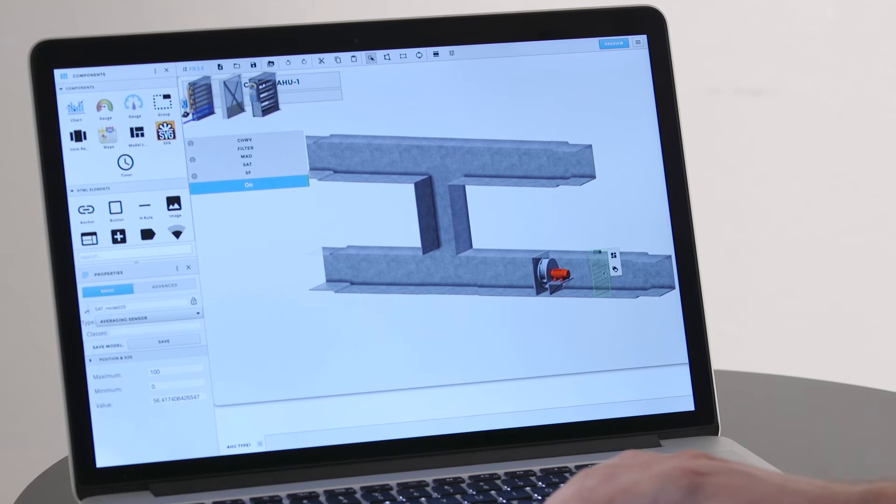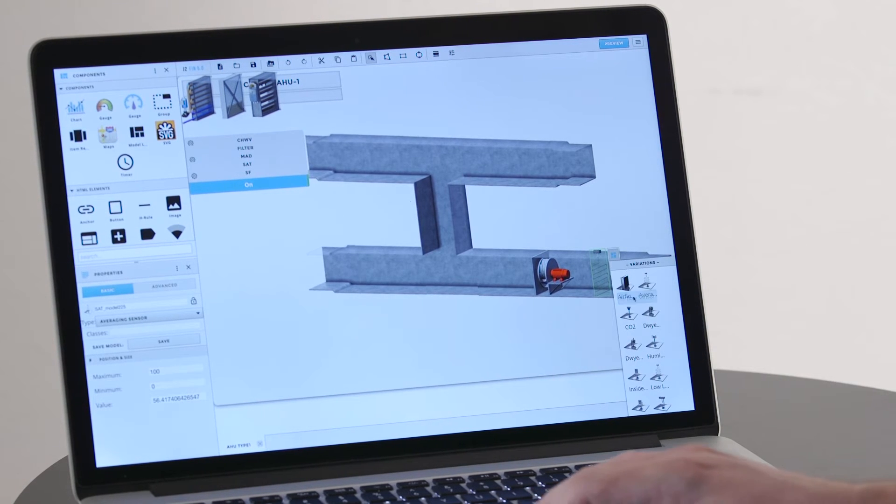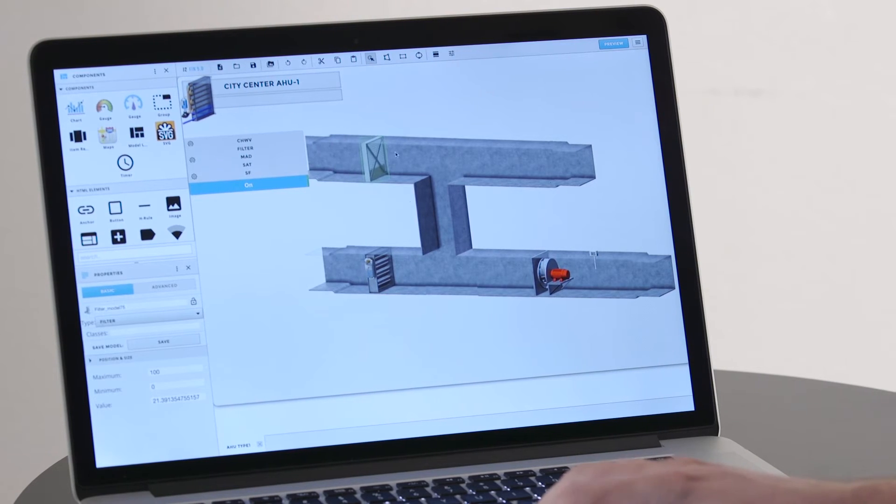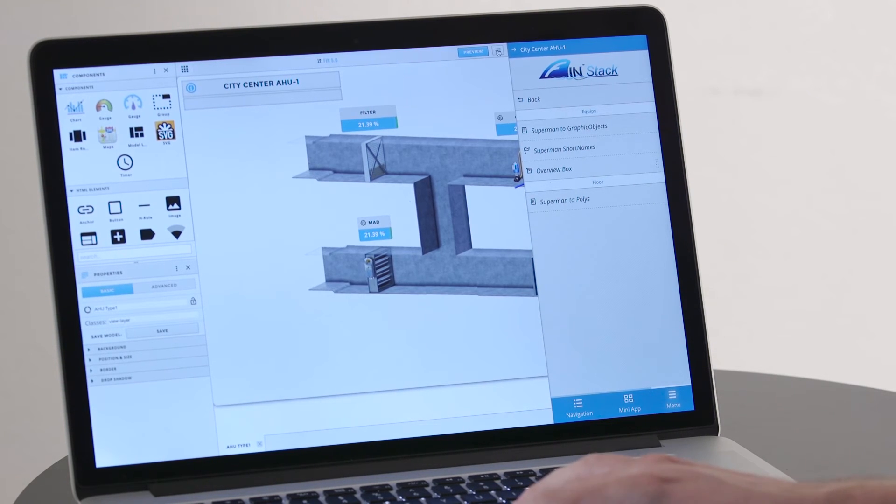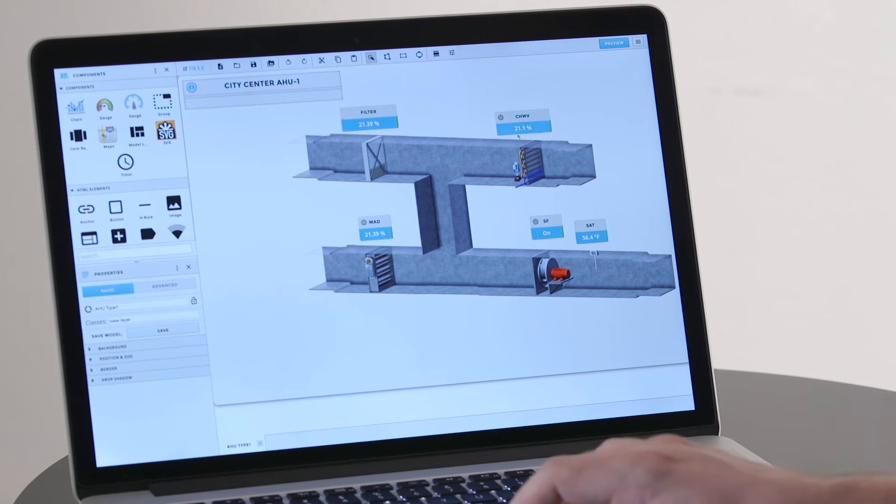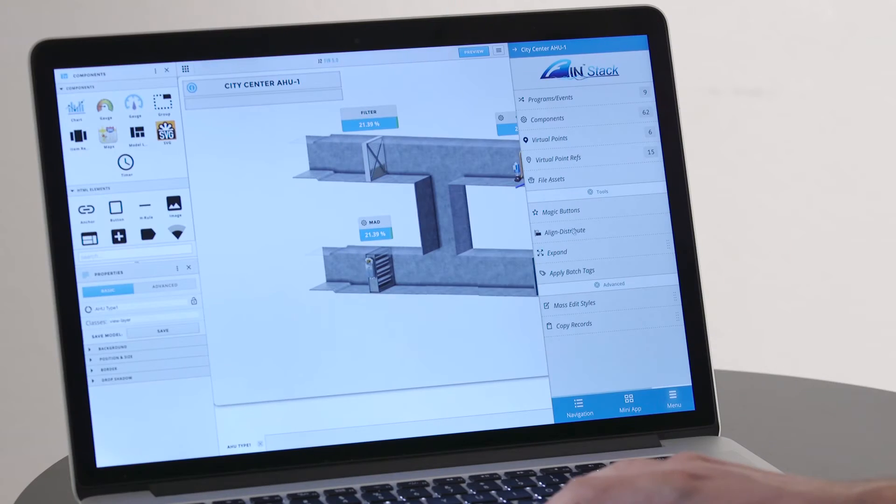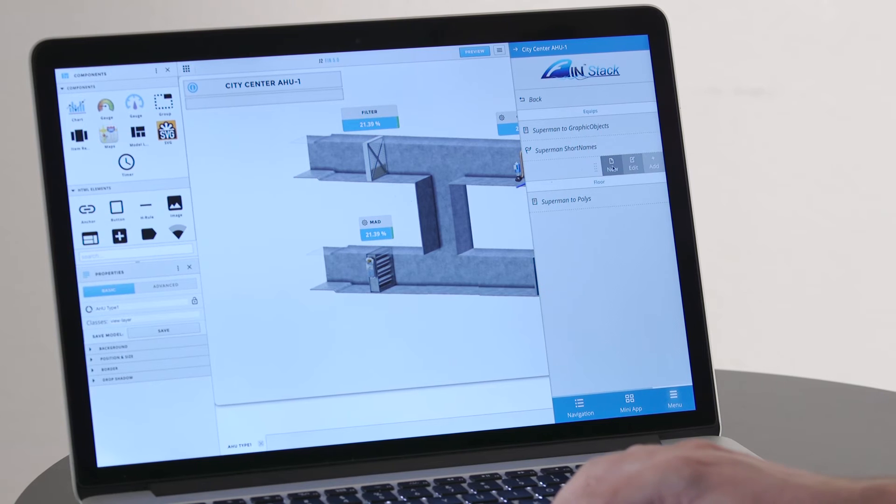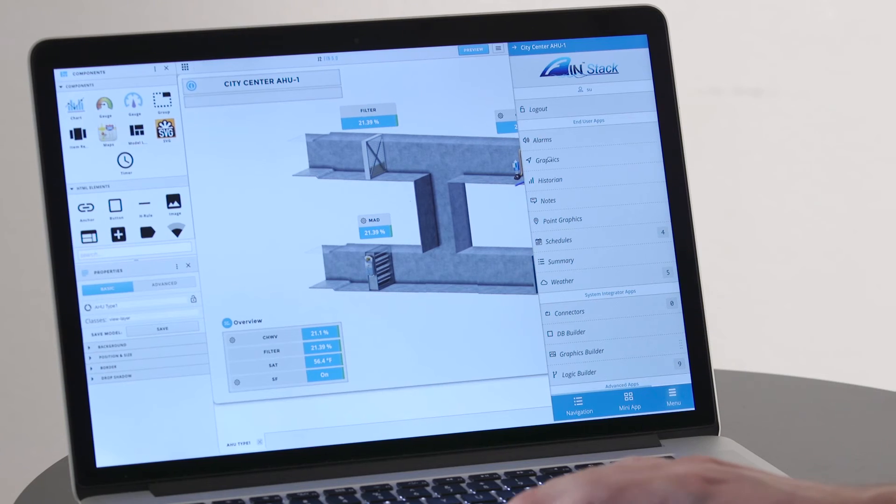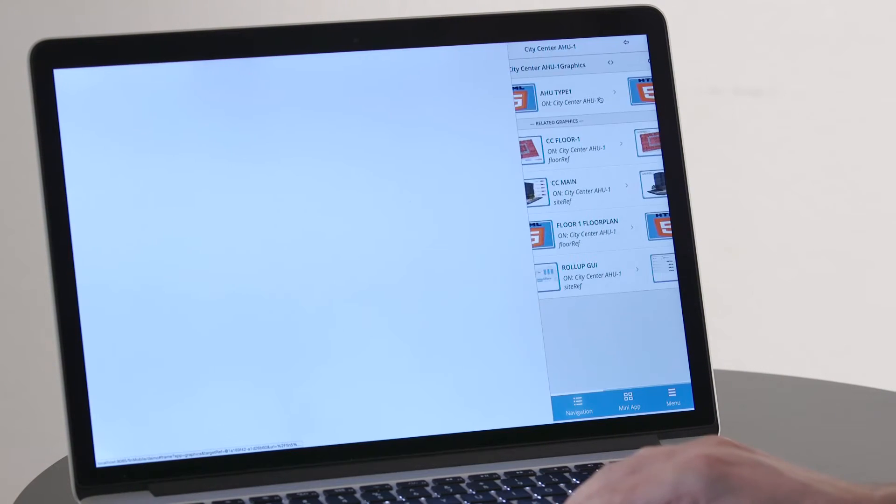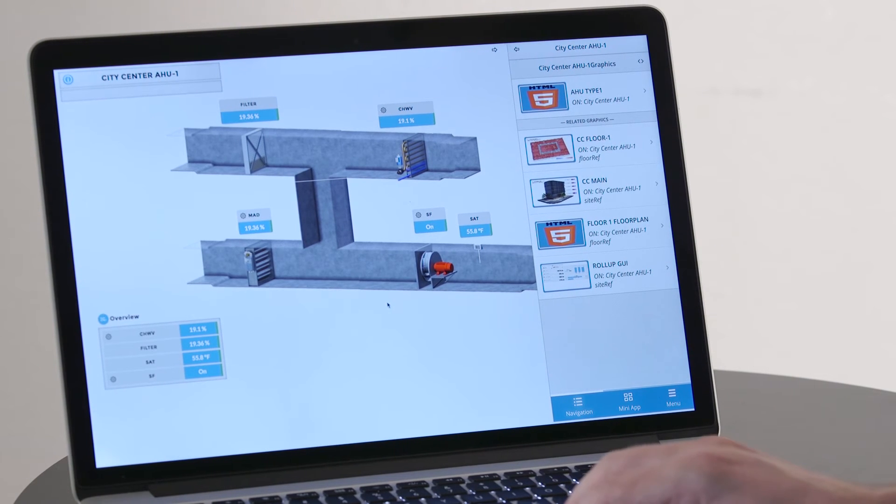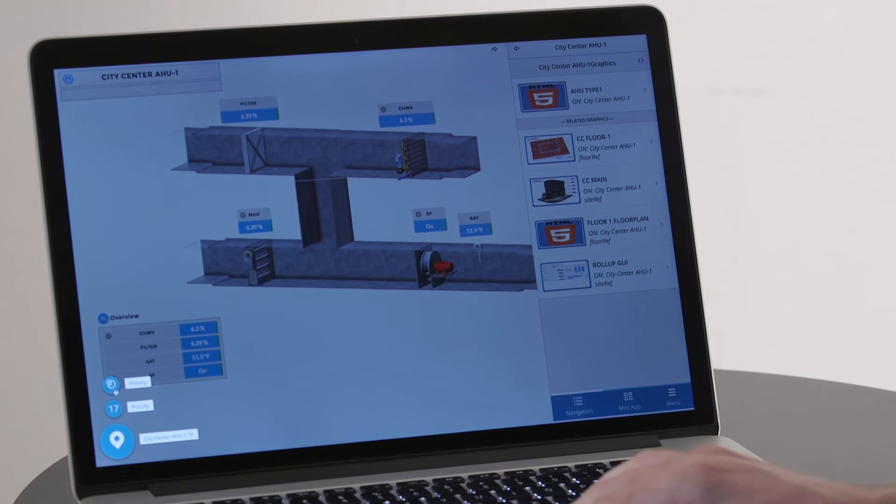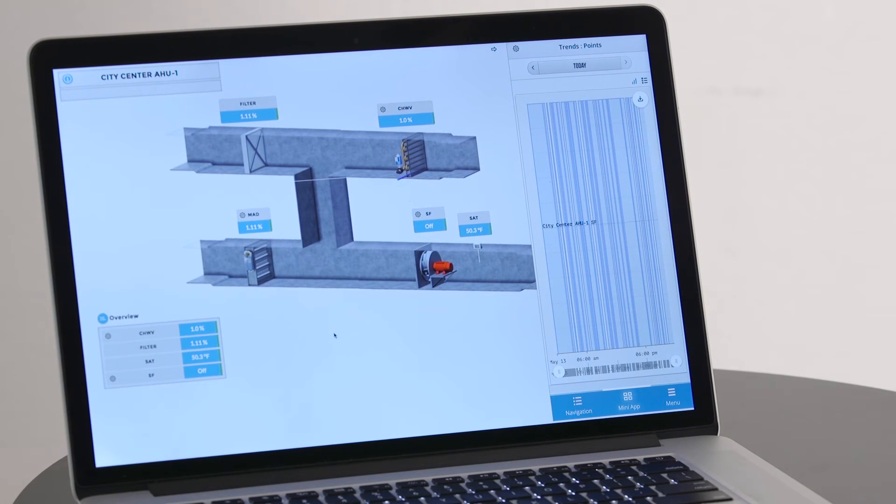If it selected the wrong graphical object, I could just click on my variations button and I could select a different sensor. So now that I arranged my graphic objects, let's go into our menu over here and use our magic button. There's a thing called graphics over here. When I click that button, it'll automatically arrange all my points. Another common thing that system integrators like to use is they like to have an overview box for their points. I'm going to go ahead and click on the magic buttons and click overview box and create a new overview box. Now that I saved my graphic, remember I'm still in city center air handler one. So if I go into the graphics app, I can now view the graphic that I just made. Remember, I didn't do anything and these magic bubbles will just work. If I click on the fan, my magic bubbles work. If I click on the history, it goes in there. I did nothing to make that happen.